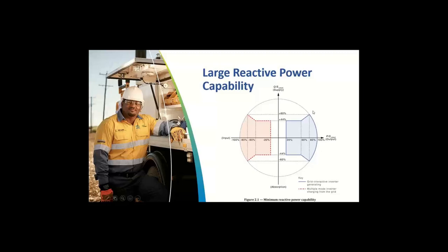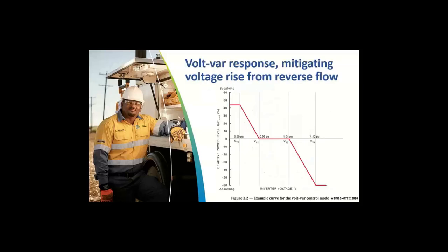And this is the capability that's required of PV inverters connecting in Australia since 2021. And so it requires substantial VAR absorption and injection capabilities during generation. What this allows us to set is volt-VAR curves. So these volt-VAR curves require an increasing amount of VAR absorption above 1.04 per unit, and also VAR injection during low voltages.